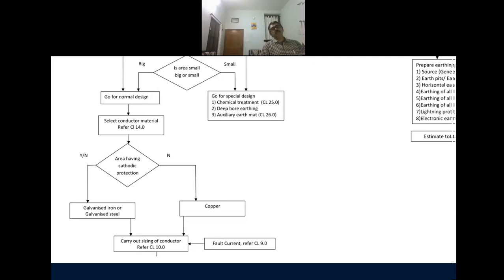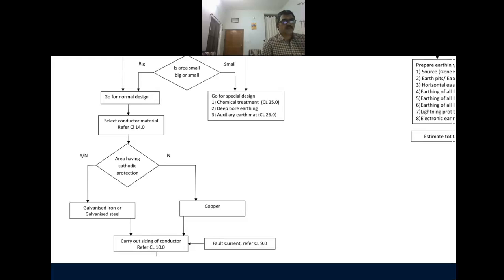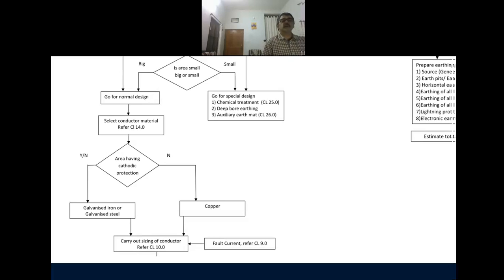Cathodic protection has two types. One is the sacrificial anode method and one is the impressed current method. When you are using cathodic protection, particularly the sacrificial anode method, your earthing conductor — if you use copper — that copper may sacrifice itself. So you have to be very careful: when there is cathodic protection, please don't use copper.